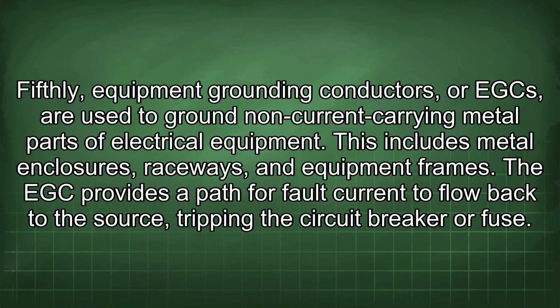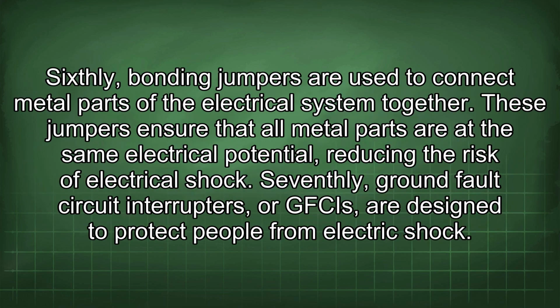Fifthly, equipment grounding conductors, or EGCs, are used to ground non-current carrying metal parts of electrical equipment. This includes metal enclosures, raceways, and equipment frames. The EGC provides a path for fault current to flow back to the source, tripping the circuit breaker or fuse. Sixthly, bonding jumpers are used to connect metal parts of the electrical system together. These jumpers ensure that all metal parts are at the same electrical potential, reducing the risk of electrical shock.